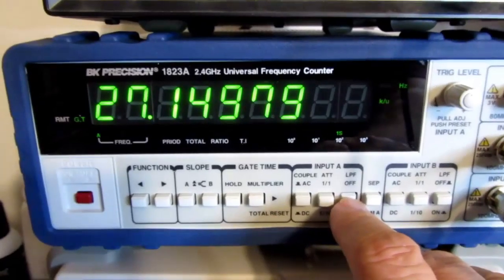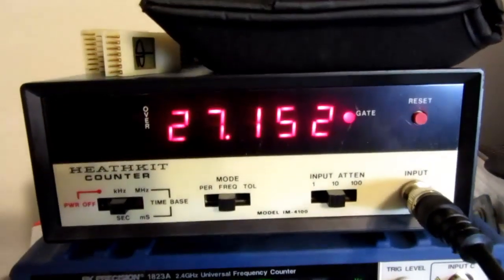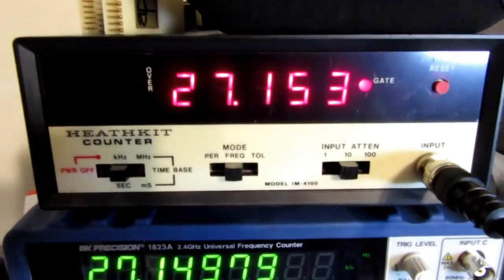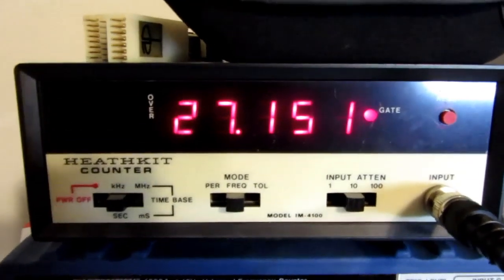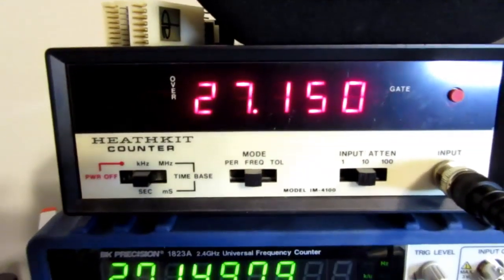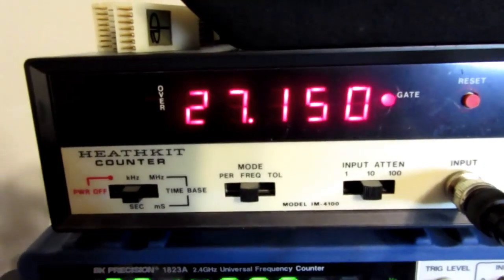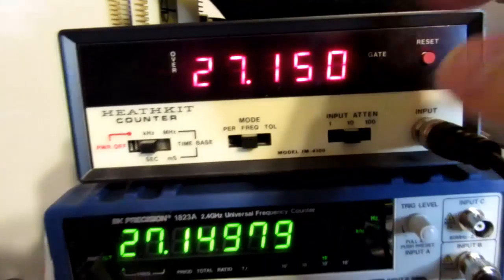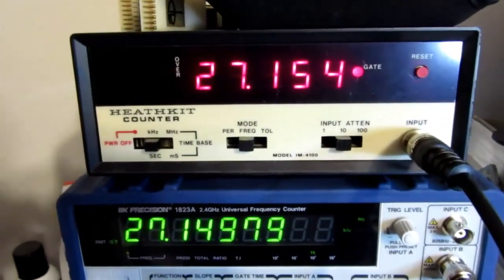And the Heathkit, even though it hasn't been calibrated in a long time, is settled in pretty nicely. When it first came on it was reading a substantially higher value, still 27 point something but it was pretty far out, and now it's settled in there pretty nicely at 27.15 and a little noise on the last digit, but not bad at all for something that hasn't been calibrated in a long time.